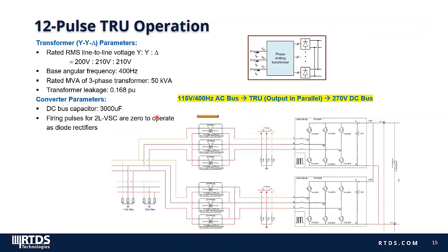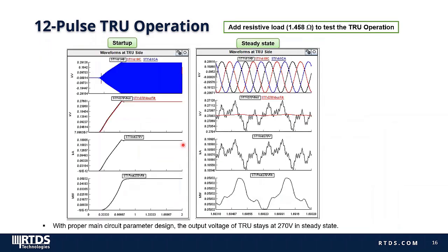Moving on to the implementation of the 12-pulse TRU: the transformers are in Y-Y-delta connection, with two rectifiers connected to the Y-connection and delta-connection windings. The rectified voltage has 12 pulses within one fundamental period. We use UCM converters with all firing pulses set to zero as the diode rectifiers. Note that the leakage of the transformer should be properly designed since the output DC voltage is tightly related to the leakage inductance. The simulation results show the TRU operating with a resistive load at 50 kW power, with the output DC voltage around 270 V.